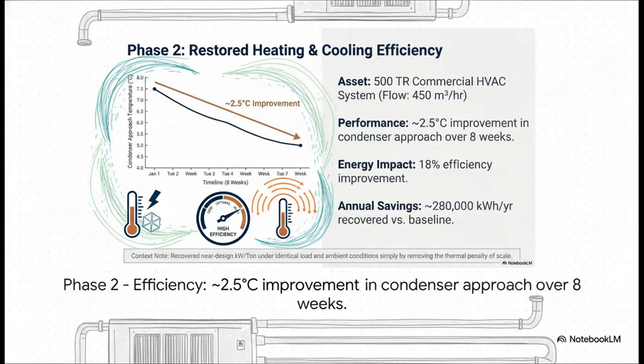So with all that scale gone, what happened to their efficiency? In Phase 2, they tracked the chiller's performance. They saw the condenser approach temperature, which is basically a measure of how hard the chiller has to work, improve by a full 2.5 degrees Celsius in just 8 weeks. This brought their system right back to its original, as-new design performance.